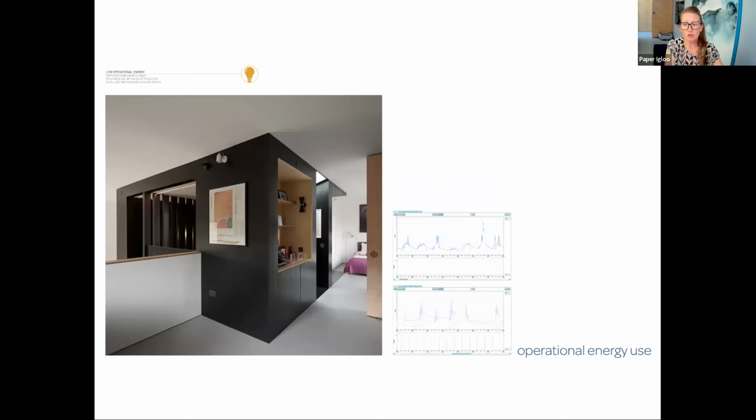We've also been monitoring our hot water generation, and these graphs show the solar thermal generation in summer at the top compared to winter at the bottom, and the correlation in winter with the immersion heater on-off in green at the base of the winter graph.